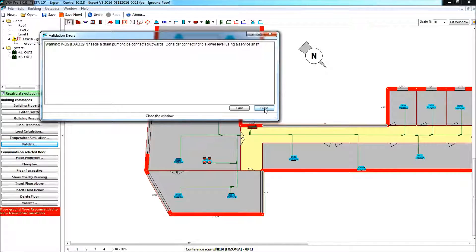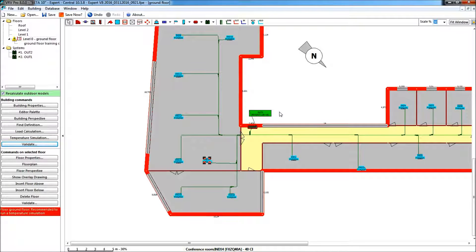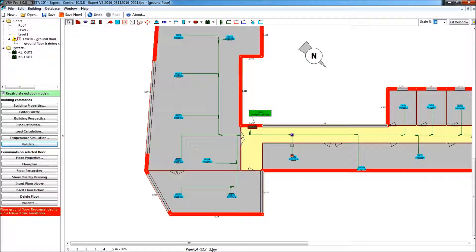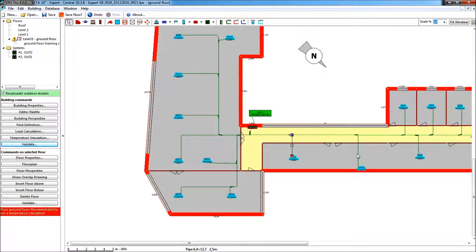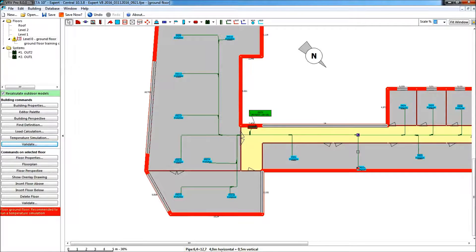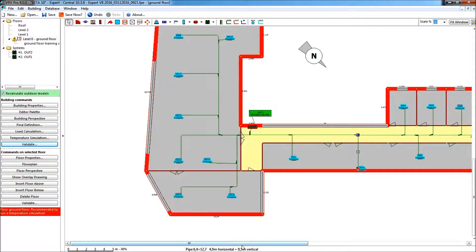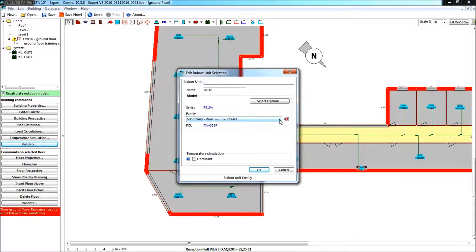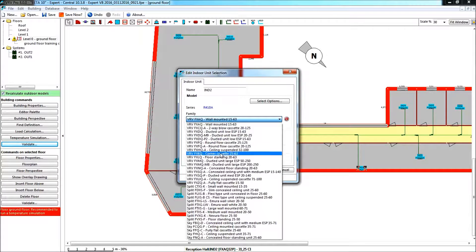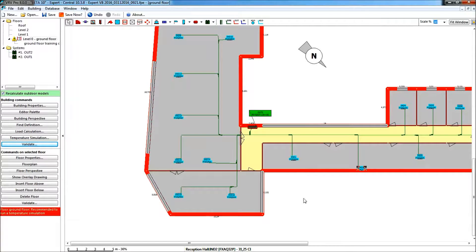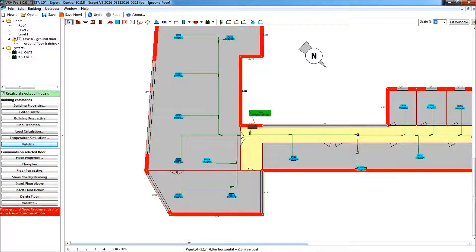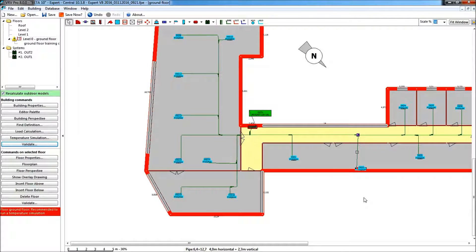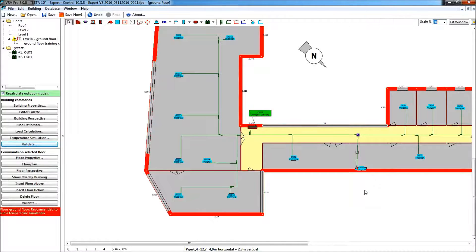What is all this, or where does it come from? There's again simply a warning, but if you look to this piping here, you see that this piping has a length of 2.5 meter. If we do the same for this unit, what do we see there? Well, we would have 4 meter horizontally, but also half a meter vertical. Now, if I would change, edit this unit, and make it a floor standing unit instead, there you would see that this pipe here would even be different, we had 4 meter horizontal still, but 2.3 vertical. So we have now in this version a far better way to control also the vertical level difference.